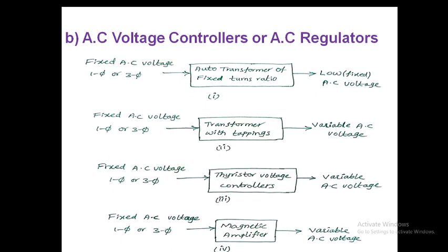The second method is a transformer with tappings: different tappings give different voltage levels, providing variable AC voltage. The third method uses thyristor voltage controllers — AC voltage controllers with thyristor switches. By controlling those switches for different firing angles, we get different variable AC voltages, applicable to single phase or three phase systems. The fourth method uses a magnetic amplifier, which amplifies electrical signals from fixed AC input to give variable AC voltage at output.